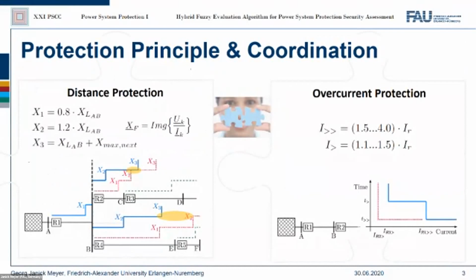The distance protection principle is based on the evaluation of voltage and current and calculates the resulting fault resistance and reactance locally at the point of installation. Based on the known reactance of the surrounding equipment, the distance from the relay to the fault can be determined. If the fault occurs in its own protection area, the relay should trip immediately. Otherwise, it can work as a time-delayed backup for following relays. Safety margins are usually considered of 10 to 20% to the end of the next protection area to ensure selective tripping.